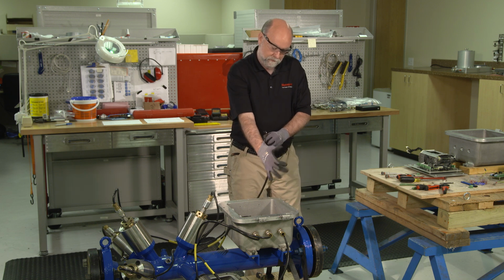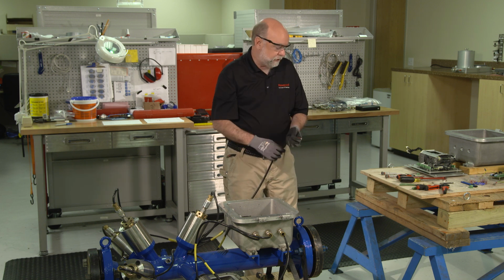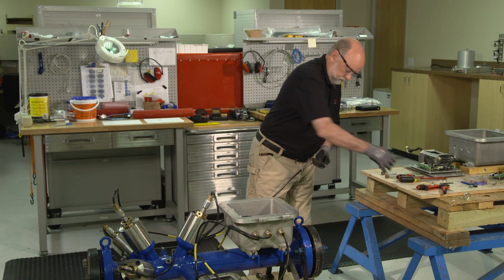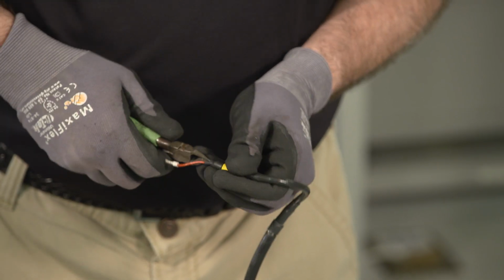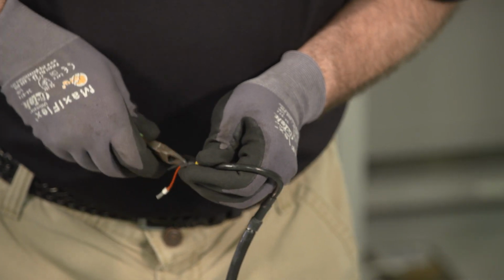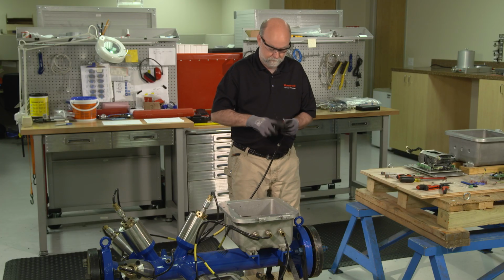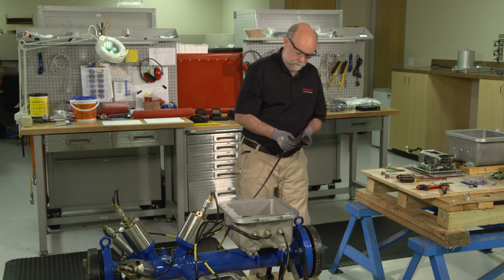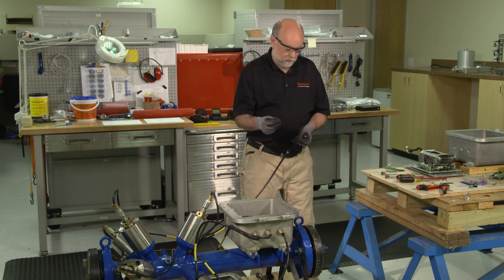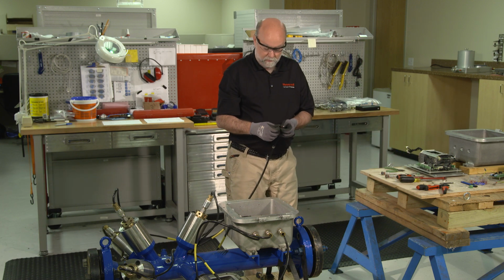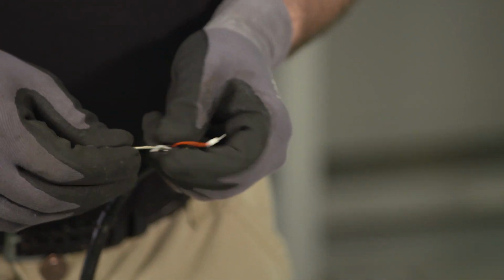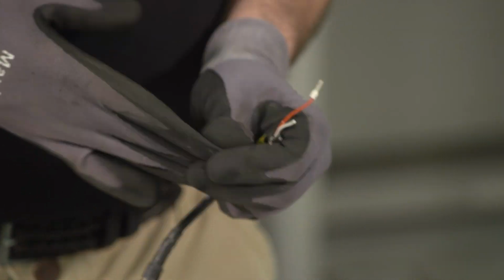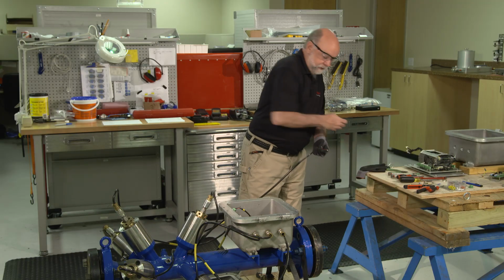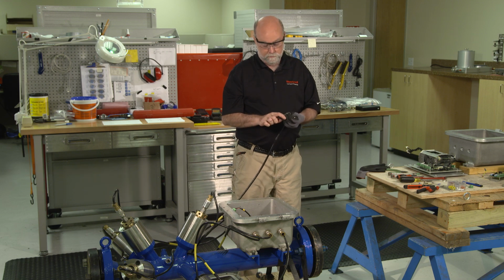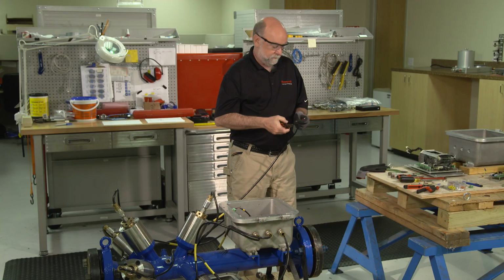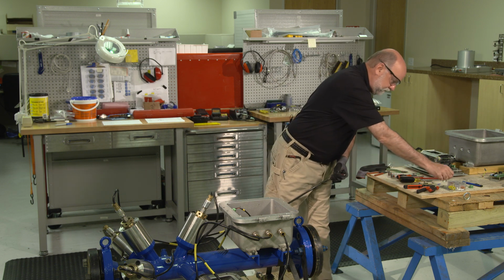My gloves back on. I've got some shrink tubing on that. I just cut that back slightly. Some wire cutters. Can pull that shrink tubing off of there. Where I've cut the ferrule off, that should actually break the connection between the white wire and the shield wire. I'm now going to strip the white wire back just a little so that I can crimp a ferrule onto it.